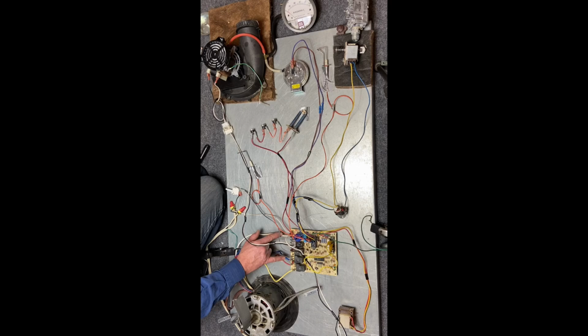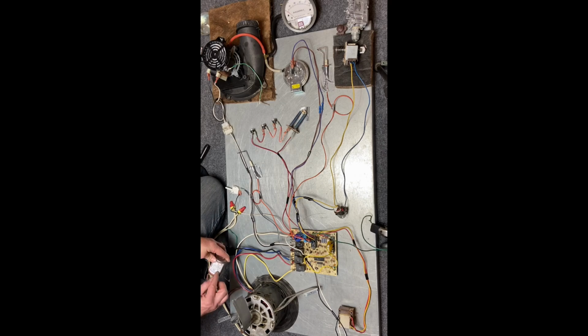Or if I want to have the fan circulating, this is low speed and neutral. And then over here I have my unused wire speed, which is probably a medium high and neutral. So I'm only using 2 wires at a time. Also for my fan motor, I'm using this capacitor. It's still 2 wires coming into a capacitor. It's very simple, 2 wires come in, 2 wires back out. So that's eliminated a good portion of this.